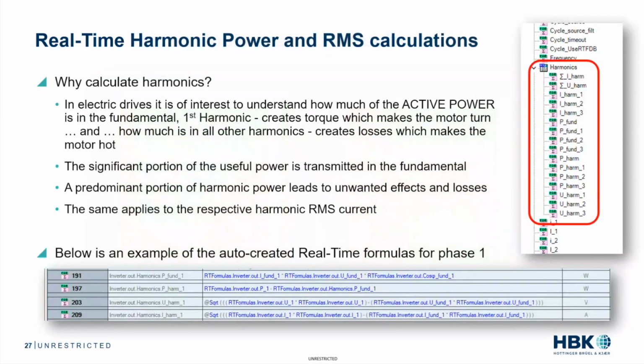Now, since we were talking about mechanical noise, let's talk about electrical noise. We've got the harmonics of power and RMS that need to be calculated. So why calculate harmonics? Well, in an electric drive, it's of interest to understand how much of the active power is in the fundamental. So you have the first harmonic, known as the fundamental. That's going to create your torque, which makes the motor turn. However, you've got all these harmonics, which create losses and make the motor hot. So the significant portion of the useful power is transmitted in the fundamental, and a predominant portion of harmonic power leads to unwanted effects and losses. The same applies to the respective harmonic for RMS current.